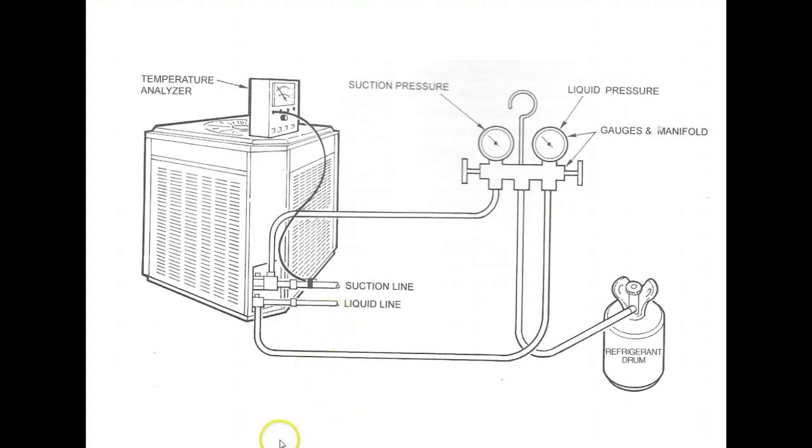The other part of hooking up the system is you're going to want to make sure that you have your temperature analyzer or your temperature gauge set up. And you're going to have it set up so that you have the sensing bulb and the temperature probe mounted about six inches away from the condensing unit on the suction line. And that is if you're measuring superheat.